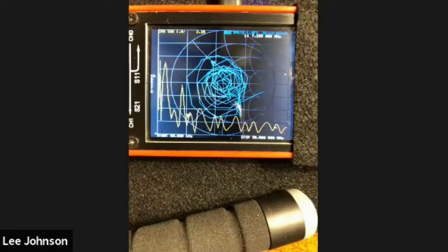And that's what part of the calibration is all about. And there's two parts to the calibration. The open, short, load part is for a one-port measurement. For two-port measurements, you have to include those three plus an additional two, which are isolation and I think a loss between the ports, because now you have 2 ports active. So you're trying to measure loss and gain and things like that. So it's a slightly more complicated calibration process. But for SWR, return loss and things like that that you're trying to measure on one port, you only have to do the open, short, and load. You don't have to do the connected through and the isolation to the second port.